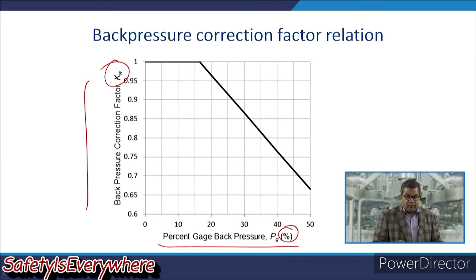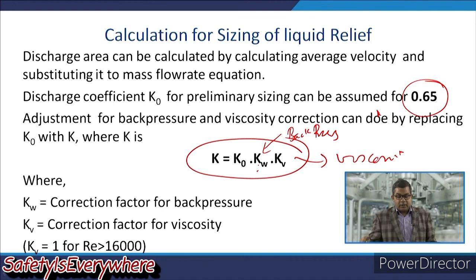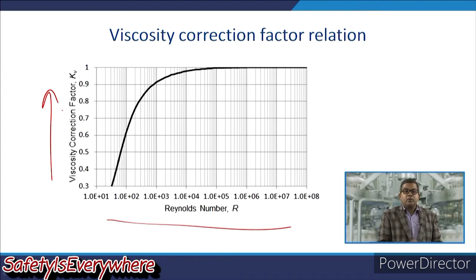So, you can calculate and have a look while you require the back pressure correction factor over this particular equation. Now, another is the viscosity correction factor relationship. Here this particular standard curve is with respect to the Reynolds number and viscosity correction factor Kv. Here on the x-axis we have the Reynolds number, and on the y-axis we have the viscosity correction factor. So, if you wish to calculate the viscosity correction factor Kv, you can do so, provided that you have knowledge of the Reynolds number.